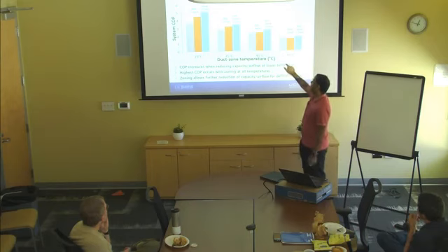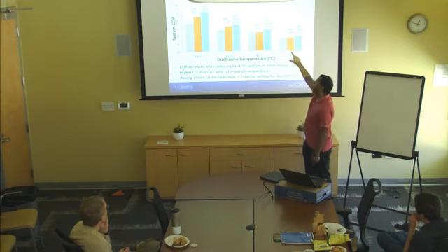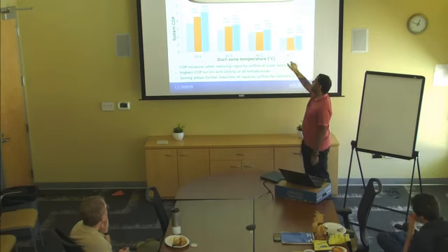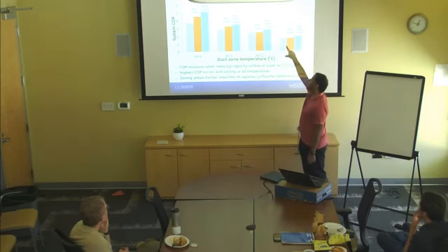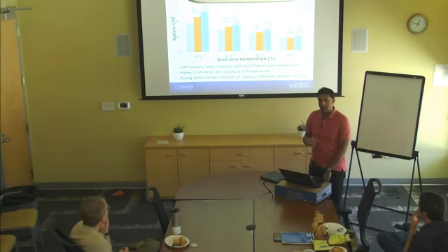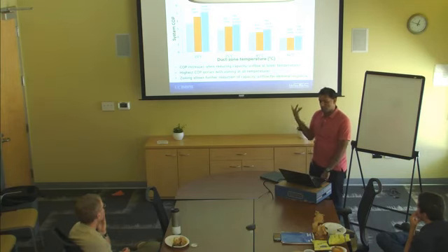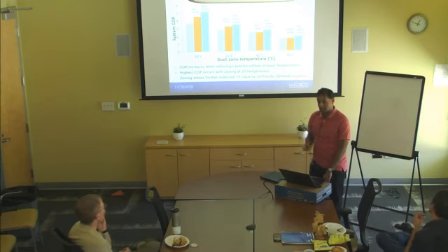What I noted was that the gray bar is almost equal in value to a situation where 40% capacity is run through one zone, which addresses the problem of demand response. So during a demand response event, a variable capacity system without zoning would actually prove negative to the efficiency. But a zoned system can allow further reduction of capacity or airflow through demand response.